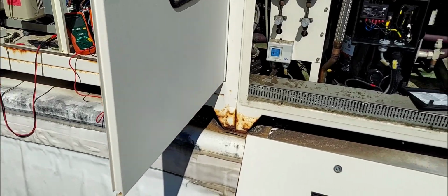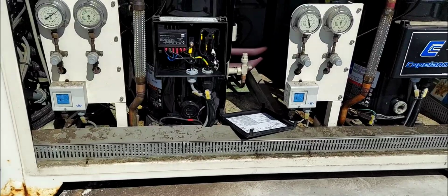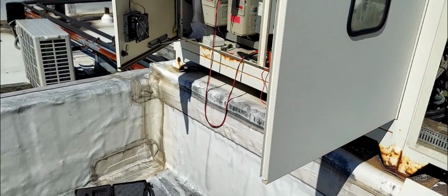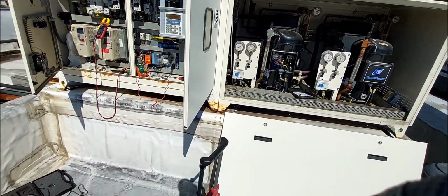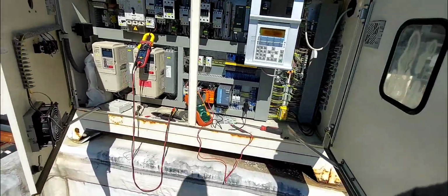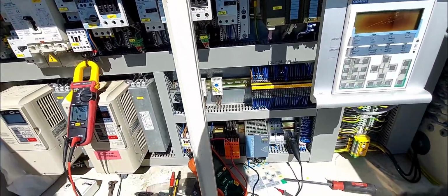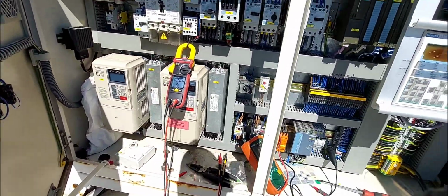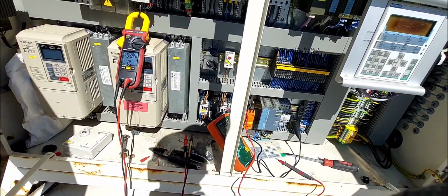Like I said, if your compressor windings' insulation is broken down and it's not completely grounded yet, it will be tripping your circuit breaker and blowing your fuses on a hot day. You'll come in, everything is cool, you replace the fuse, you reset the circuit breaker, and then two days later you're back on the same call. You've got to run a Meg test on that motor. Yeah, so that's pretty much it.